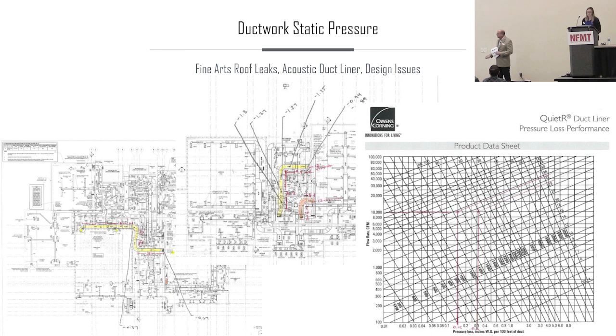A little bit of an examination. I'm pulling the paperwork on when this was built. What the heck? Because it seems very odd that the builder was ever even walking away from it with it behaving this way. And as it turns out, it became apparent that the duct sizing was absolutely correct for standard duct. But the minute you put the acoustic liner in it, you've changed the duct airflow characteristics. And to overcome that airflow, the air handler is ramping itself to max speed.